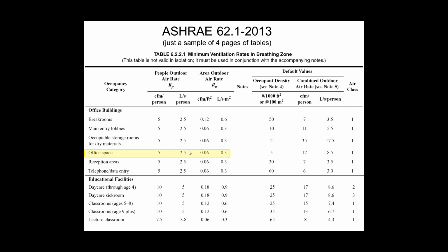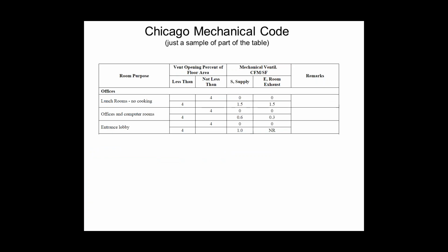Right now that's in two separate pieces. It was done that way specifically to allow us to do things like demand control ventilation. I can now modulate this 5 CFM per person part and still maintain the 0.06 constant times square footage, and allow me to modulate the ventilation air back as the CO2 levels change. So that's a specific reason for separating these. There may be other reasons, but in 12 years, nobody can tell me any other reason we separated them other than for CO2 demand-based control ventilation.